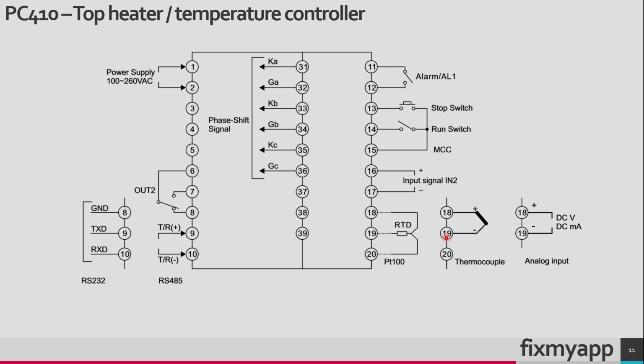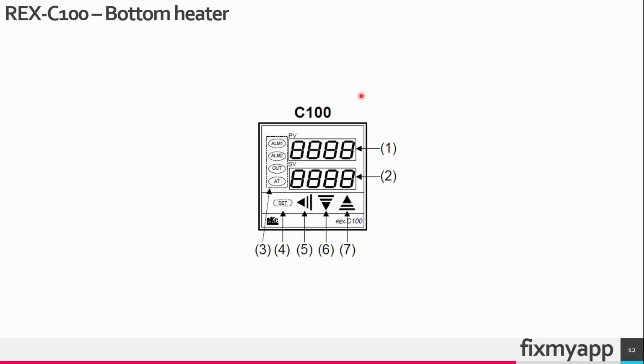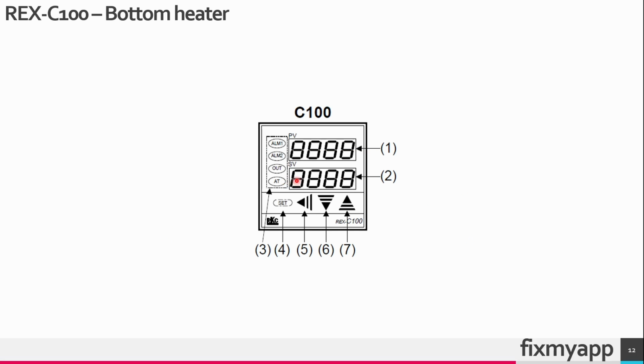Be aware that you have to connect the positive lead to terminal 18 and the negative lead to terminal 19. This is the temperature controller for the bottom heater, the REX-C100. The REX-C100 is a digital temperature controller suitable for different applications where precise temperature control is required, such as industrial ovens, furnaces and incubators. In this case, it will be used as a preheater that will drive 2 or 4 ceramic heating plates for the bottom heater.